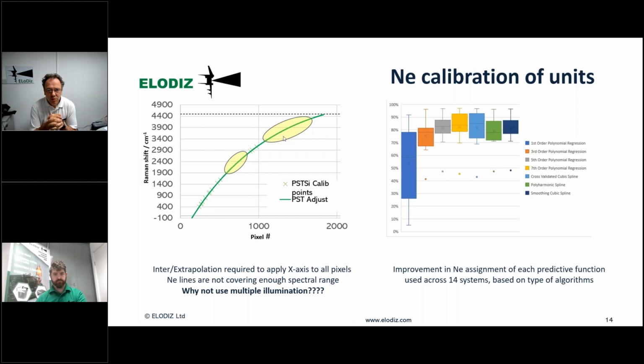Some users have asked why we don't use multiple illuminations, for example mercury lamps. The problem is that the precision and use of certain lamps is not for every user. This protocol has been created with everybody in mind, to put it in a very broad way, and it is not easy to use certain lamps for everybody. For that reason, we have centered on only one type of illumination, which is neon. The protocols cover mostly two wavelengths, 785 and 532, which is approximately 80% of the market.